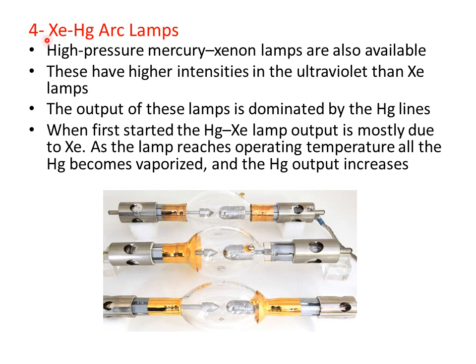Another light source is the xenon-mercury arc lamp. High pressure mercury-xenon lamps are available and have higher intensities in the ultraviolet region compared to xenon lamps alone. Their output is dominated by mercury lines. At startup, the output is mostly due to xenon, but as the lamp reaches operating temperature, all the mercury becomes vaporized, so most of the emission is then due to mercury.